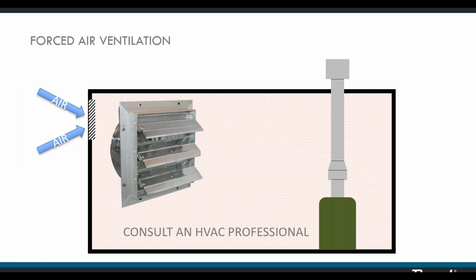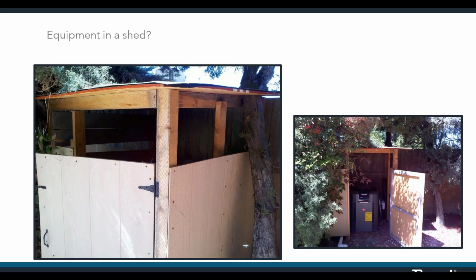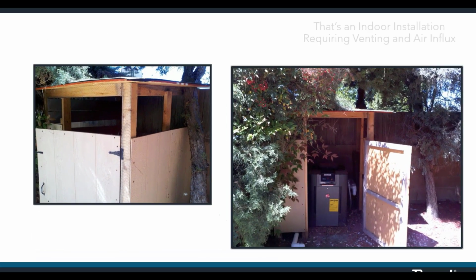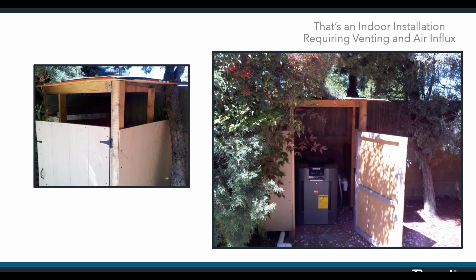Forced air ventilation. If you're installing a heater, often you'll find swimming pool equipment that's installed inside a structure or a shed. Whether you're installing it in that way or whether after the equipment was installed, someone built the shed around it, doesn't matter. That's now an indoor installation. That's going to require a vent hood and correctly sized air intake openings, not only for the sake of proper performance, but for safety. We don't want anyone using this small space to suffer from inhalation of fumes.